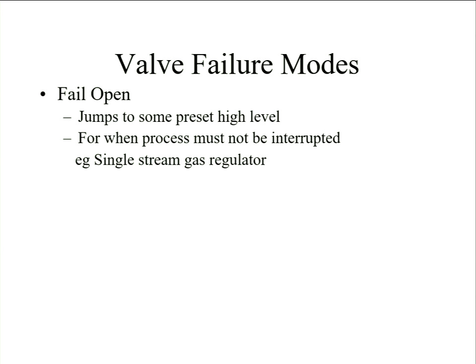So you get so-called direct acting, so the more you increase the input, the valve will go further open. So if it was, let's say, a 4 to 20 milliamp electric interface, 4 milliamps is closed, 20 milliamps is open, but you can have it the other way around. 4 milliamps is open, 20 milliamps is closed. So so-called reverse acting. And I've seen that confuse people. Why is that working in that direction rather than that direction?